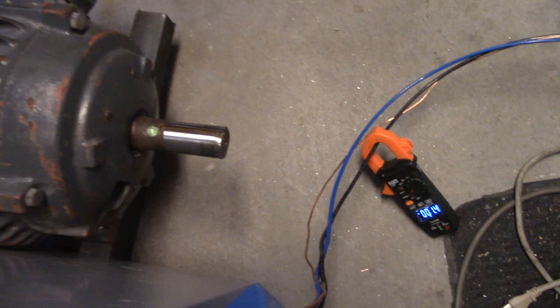I also got a new clamp meter. We're gonna go ahead and put this onto max mode, and we're gonna put this on the single phase line right here. We're gonna probe the A line for now. We're pulling like 1 amp right now - I don't know why, that's because I put the thing on. But we're gonna go ahead. I'm gonna hit the start button and watch the motor and the meter start up.